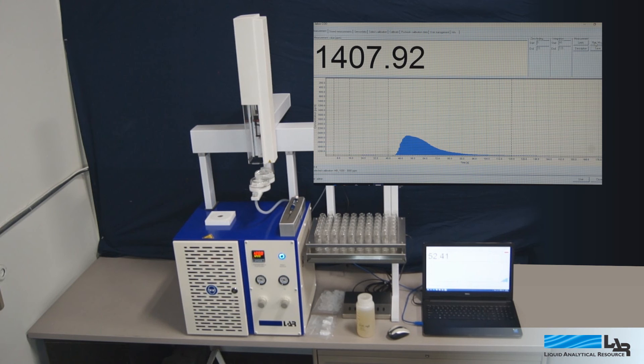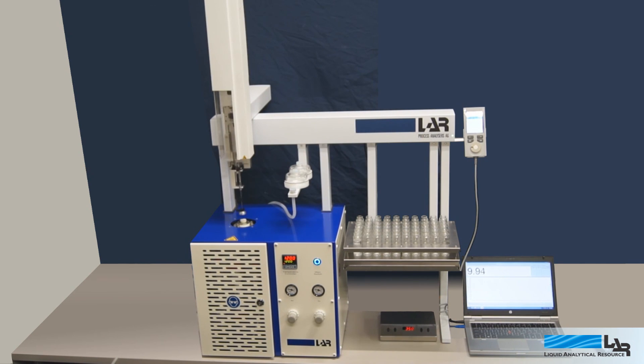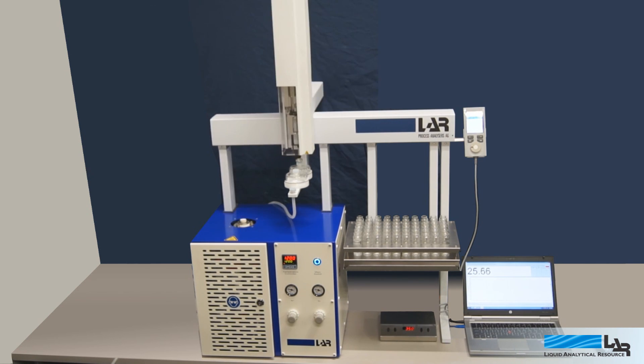The QUIC-COD lab has an optional autosampler. The sampler holds 60 sample vessels, each with its own magnetic stirrer. The autosampler enables the analyzer to run up to 60 samples unattended, freeing staff to perform other tasks. It can also be programmed to measure each vessel in replicate, enabling improved accuracy through the elimination of outliers.